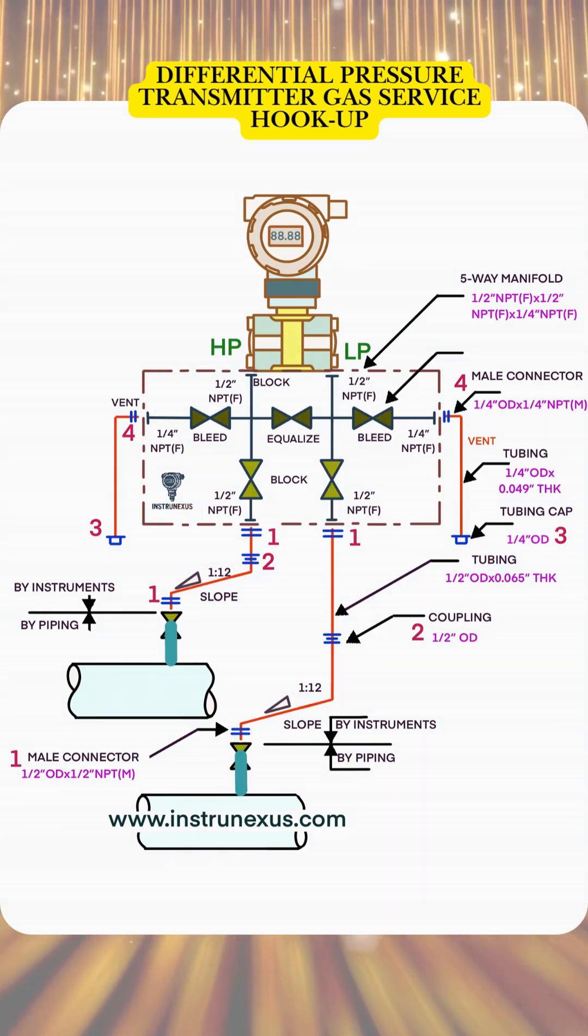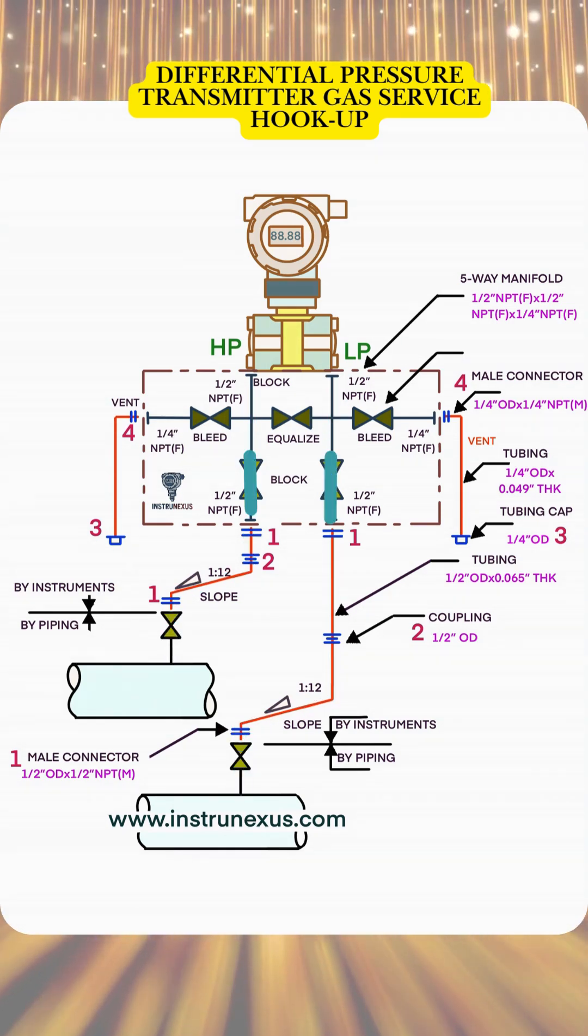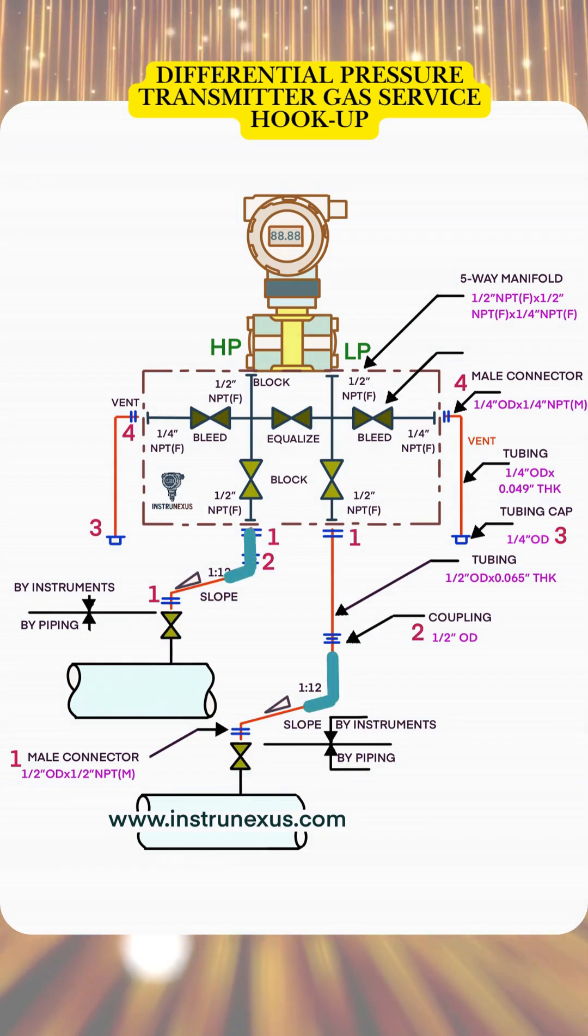The manifold includes two block valves to isolate the transmitter, one equalizing valve to balance the pressure, and two bleed valves for venting and calibration.